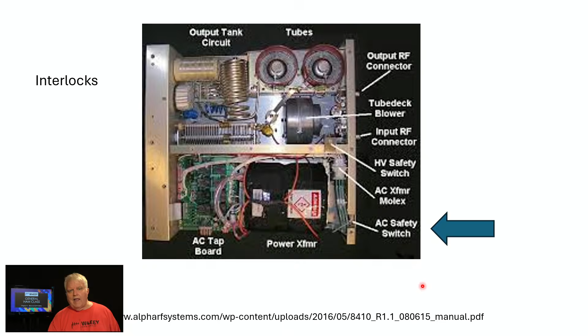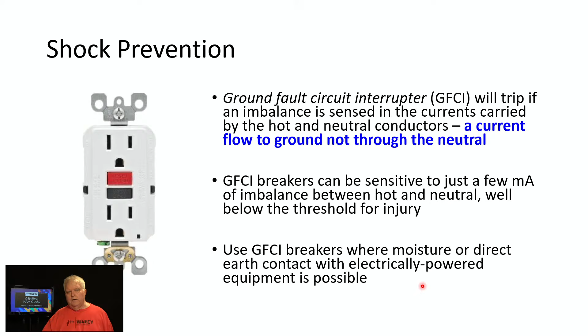Something that's popular now in home wiring, because of its great potential to save lives, are ground fault circuit interrupters. GFCIs, you've seen them like this, are typically in bathrooms, garages, kitchens, and the idea is that they have very sensitive measuring instruments inside, measuring the current that's going out of the black wire and comparing it to the current that's coming back on the neutral lead, because that's the current that is doing work in whatever is plugged into the outlet. If, however, there's more current going out of the black lead than there is coming into the white neutral lead, that tells the GFCI that there's stray current going somewhere. That stray current might be going through a human, and I better shut down.